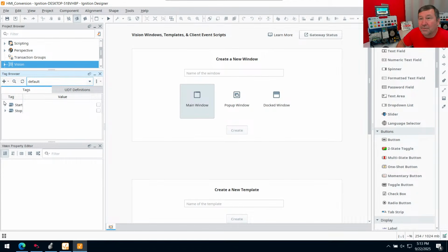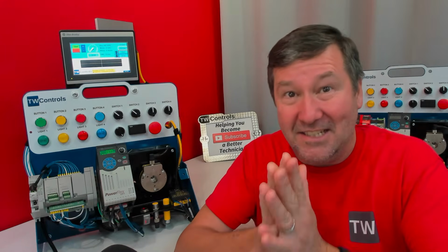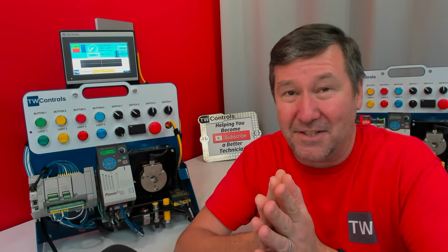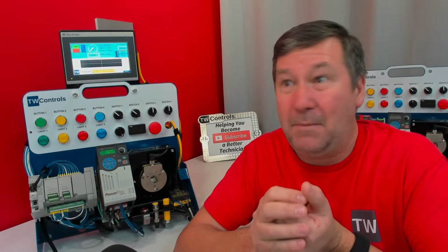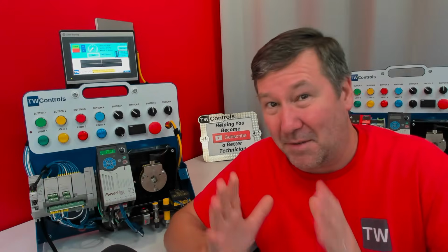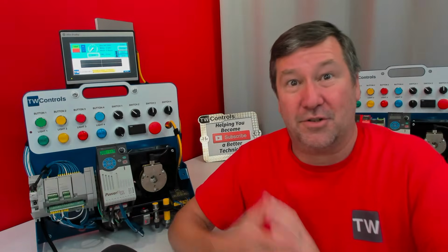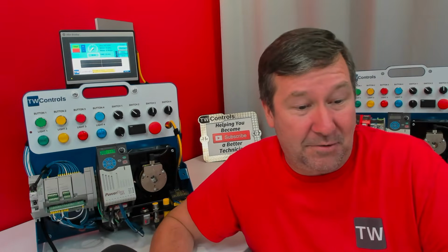All right. And here's what I mean. Again, the one thing I love about Ignition is every step of the way we get instant verification. If it doesn't say an error right here, this is live data. And we can actually use these. And one thing we talk about a lot in our training class is sometimes Ignition is awesome, even when you don't actually need to build an HMI or SCADA. Let's say we didn't even have the software. Well, first of all, we can pull live data, and maybe we just need to stick a temporary trend on something that's running a different SCADA system. If we don't want to mess it all up, we can start a trend there. We can have it just running on our local computer and do a lot of good troubleshooting on it.